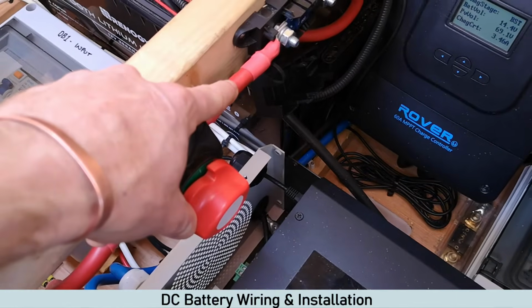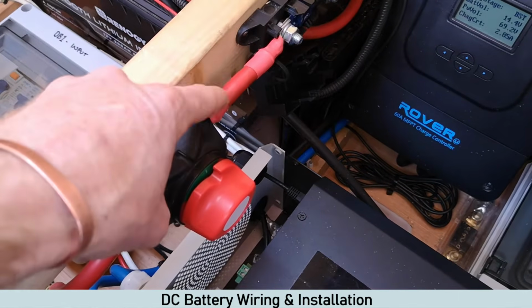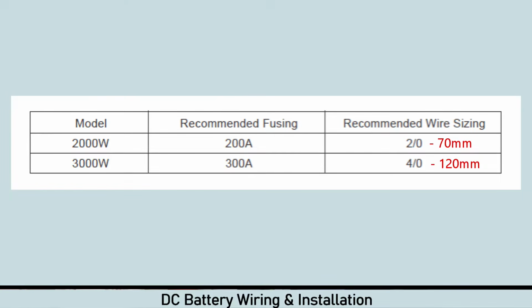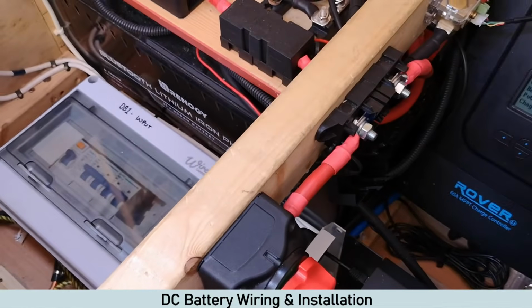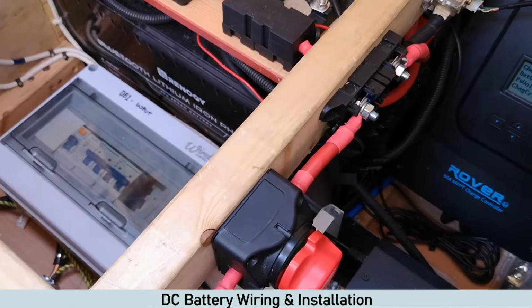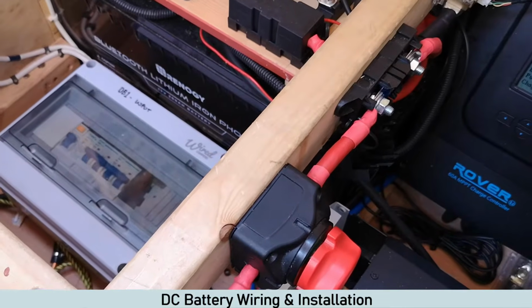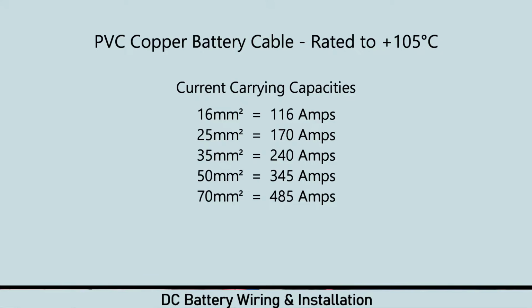We're using 35mm cable. If you go to the manual, each manual, whether you've got the old one or the new one, they all state that for the 2000 watt you need 70mm cable, and for the 3000 watt you need 120mm cable. So if you actually go to the cable manufacturers, a 35mm battery cable, ours, which I'll show you here, is rated at 240 amps. So that's more than enough.